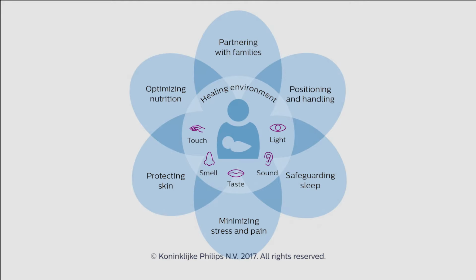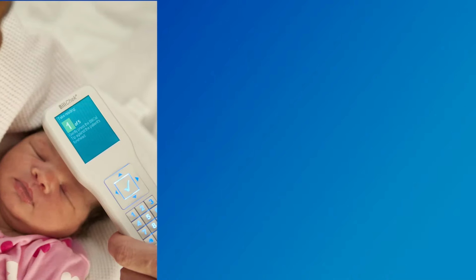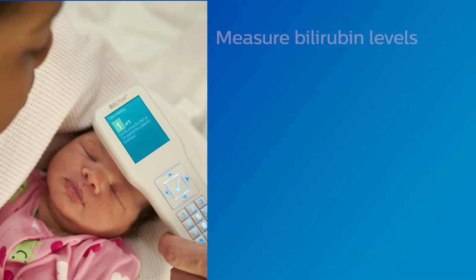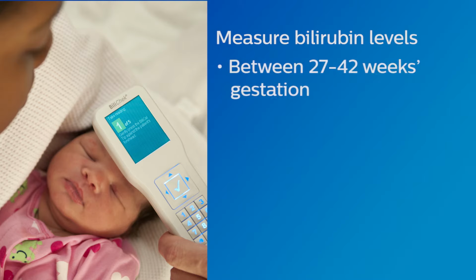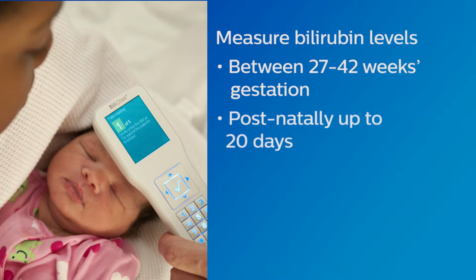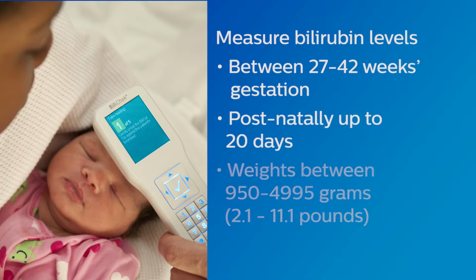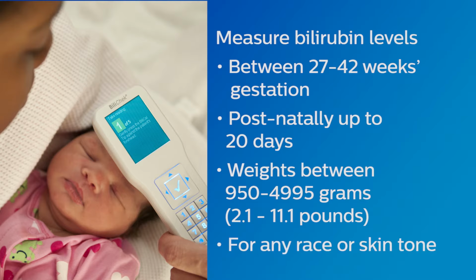Utilizing the Bilichek aligns with the core measures for neuroprotective family-centered developmental care outlined in the Philips Neonatal Integrative Developmental Care Model. The Bilichek provides the unique advantage in that it can be used to measure bilirubin levels in neonates between 27 and 42 weeks gestation, and postnatally up to 20 days of age in neonates weighing between 950 to 4,995 grams, or 2.1 to 11.1 pounds, of any race or skin tone.